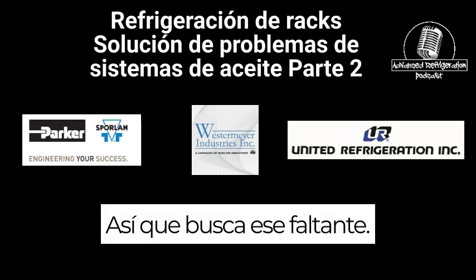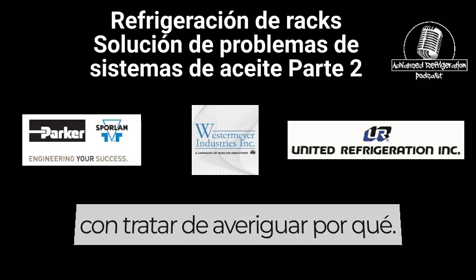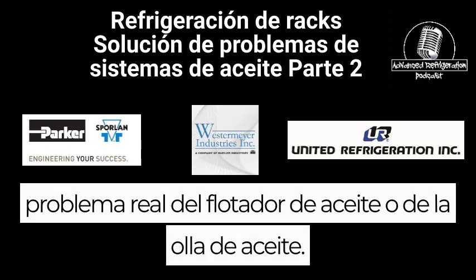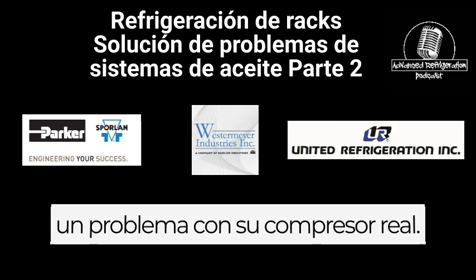So if we have an elevated crankcase and we have an elevated reservoir, there's no flow. So look for that misting. That will help you out immensely with trying to figure out why it might not be feeding oil. Like I said, it might not be an actual oil float or oil pot issue. It might be that you have an issue with your actual compressor.